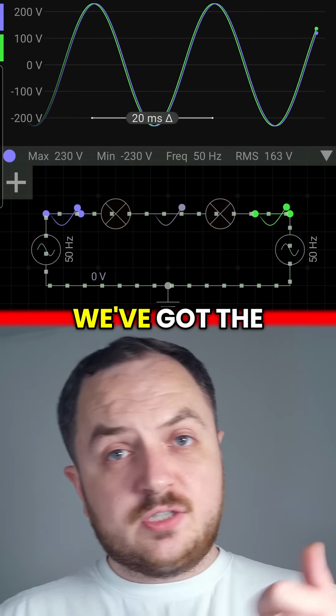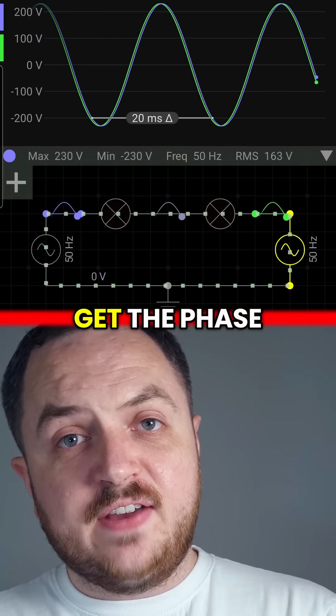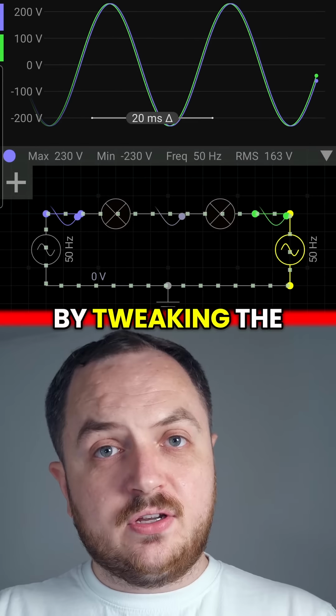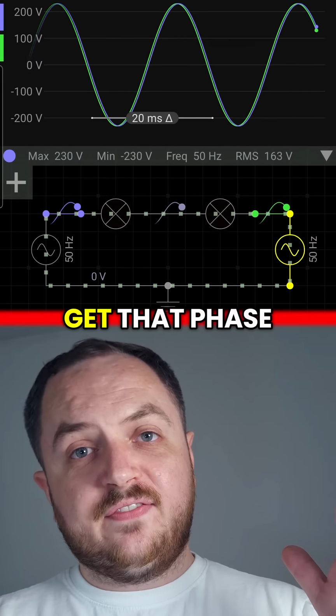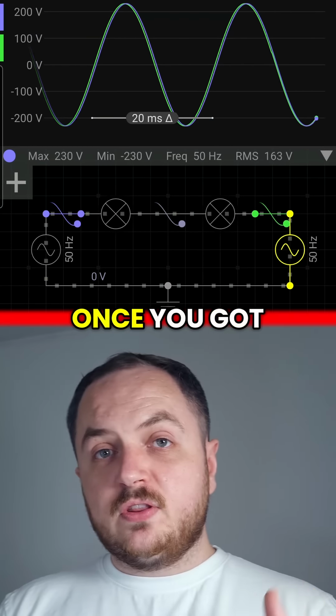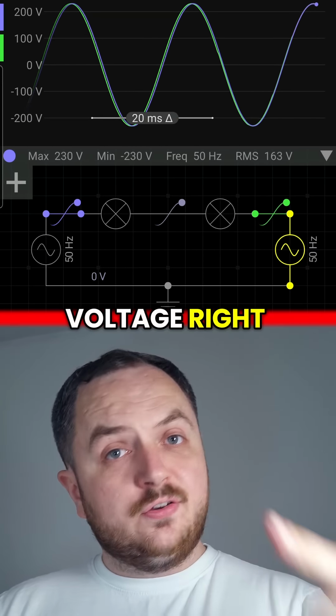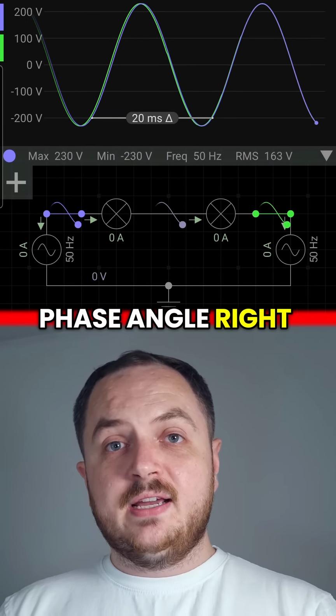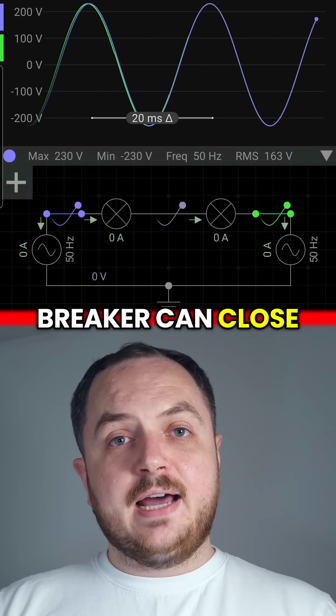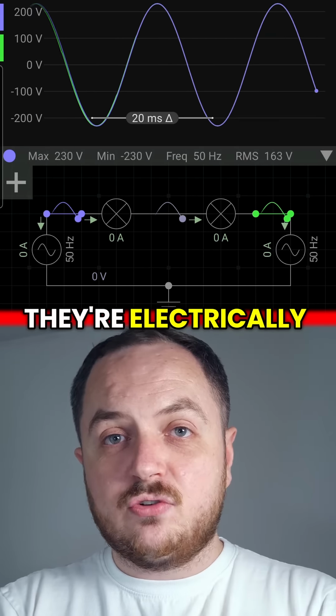And then finally, we've got the speed right, we've got the volts right, we need to get the phase angle right, and that's just by tweaking the governor just a little bit till we get that phase angle down to 0. So once you've got the phase sequence right, the voltage right, the frequency right, and the phase angle right, then the generator breaker can close and parallel both supplies so they're electrically locked in.